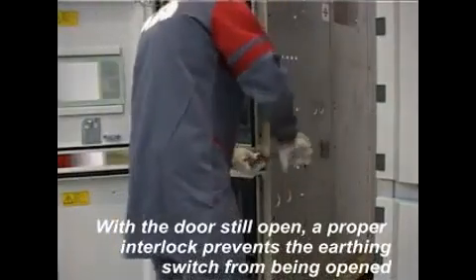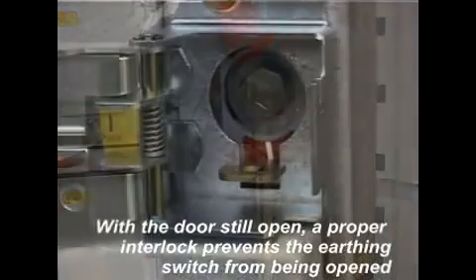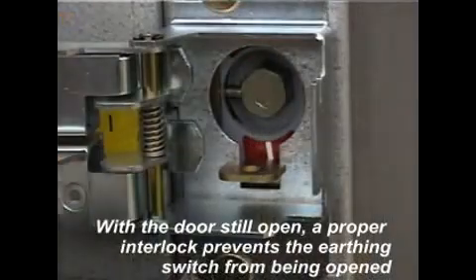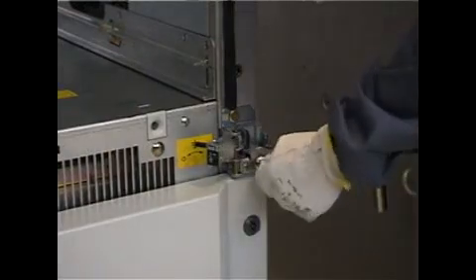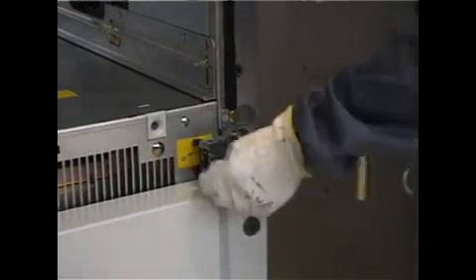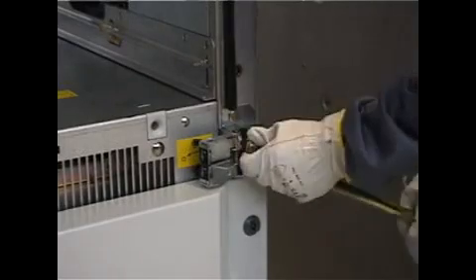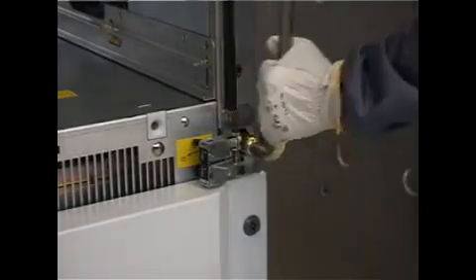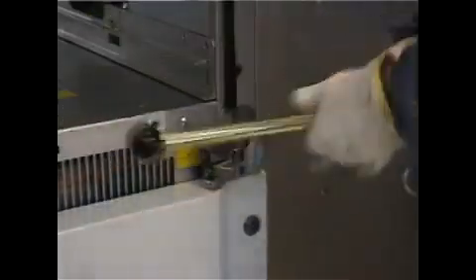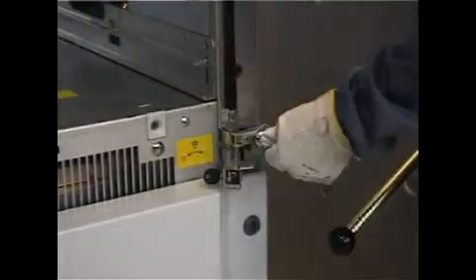An additional safety lock prevents the earthing switch from being operated while the door is still open by obstructing the access to the shaft. Now we can close the door, insert the key to be able to open the earthing switch and operate on the key lock to prevent anybody from closing it again.